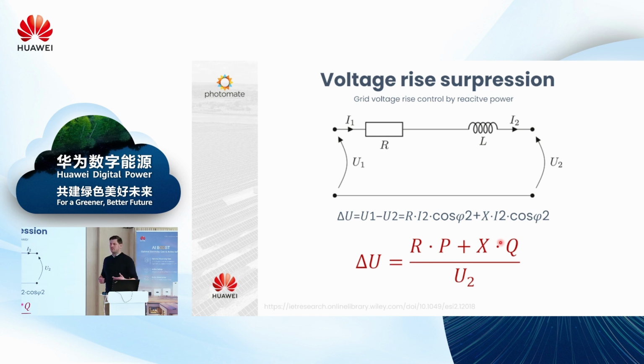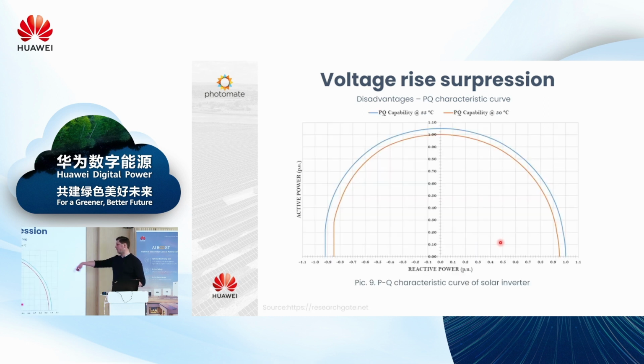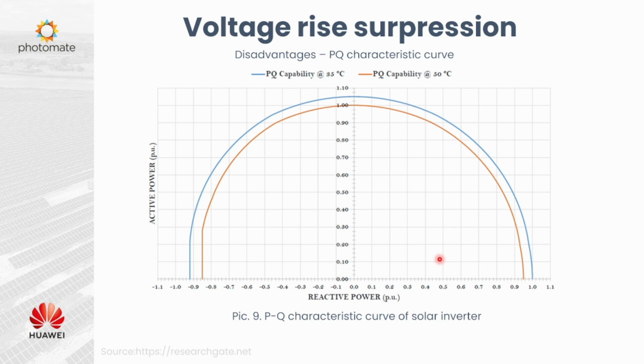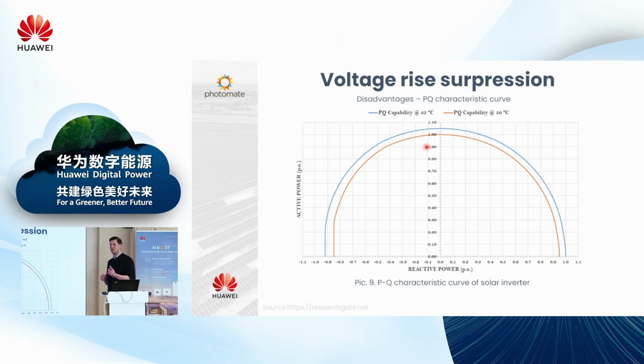There is also a disadvantage of this, because this is the output curve of the inverter. Each inverter, doesn't matter, you can pick any, central inverter, SolarEdge, whatever. It's how the active power is related to reactive power. So here we have our active power and here the reactive power. If we just enable the function and just imagine we are at this point, maybe this one, okay? It means our active power potential has been reduced by 10%. So your inverter cannot produce right now 11 kilowatts, but 10. So this is the negative point of using this function. But still, after some calculations we did together with Huawei, it's the most profitable and legal solution to your problem with the grid over voltage.